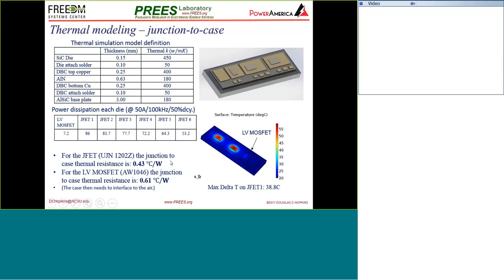The worst case is about 0.43 degrees C per watt from the top of the die to the back side of the AlSiC. For the low voltage MOSFET, because the FET is smaller you actually have a higher resistance, but you only get 7 watts, so that's a non-starter. That's junction-to-case.